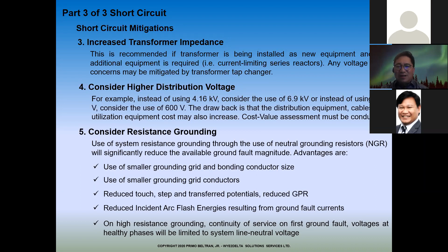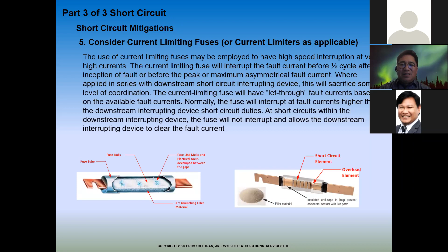What are the other mitigations? Like I said earlier, you deliberately clip the current by not allowing it to reach half cycle so it doesn't reach peak, and you need a very fast clearing time. Current limiting fuses can do that. These current limiting fuses have magnetic properties wherein as the fault is still rising within the half cycle, it gets interrupted in less than half cycle.